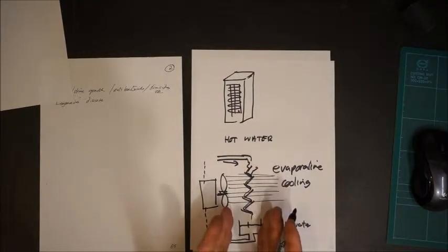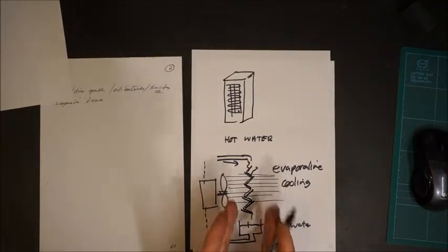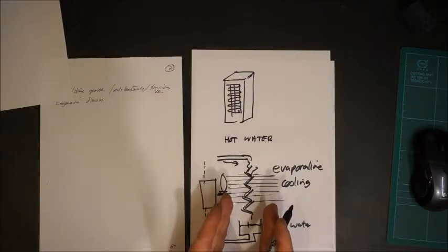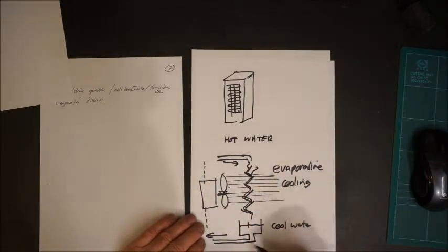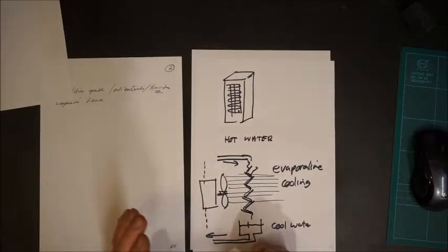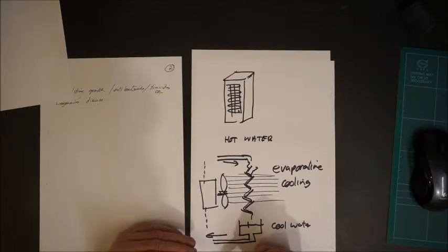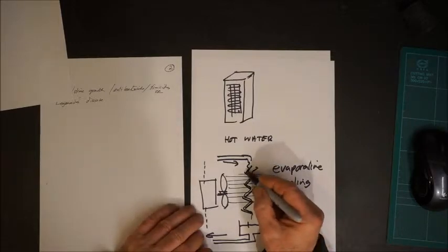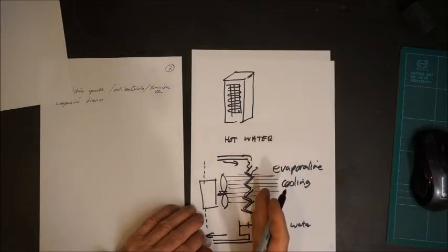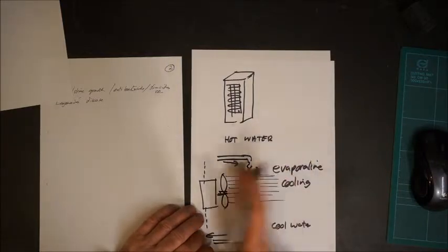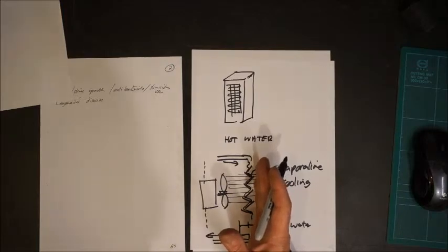Now this water is never completely cold, it's usually slightly warm. And this is a perfect place to grow bacteria, to grow all kinds of obnoxious things. Also, any dust with soluble minerals is going to get in here, so the cooling water which goes back is often a bit dirty. So you've got to maintain it, you've got to filter it, you've got to add things to kill the bacteria, to kill the slimes, the various amoeba and molds and yeasts and other things which will grow in this nice warm water on the plates. If you don't do that, the whole thing becomes very contaminated very quickly.